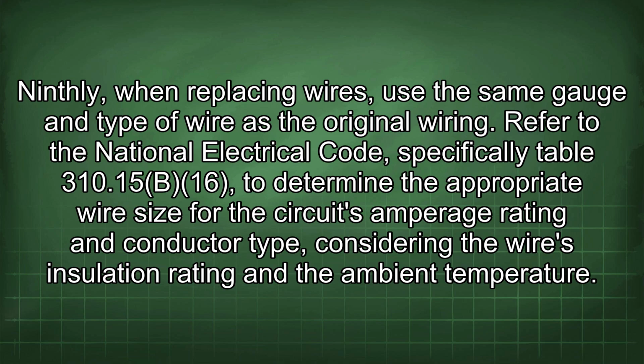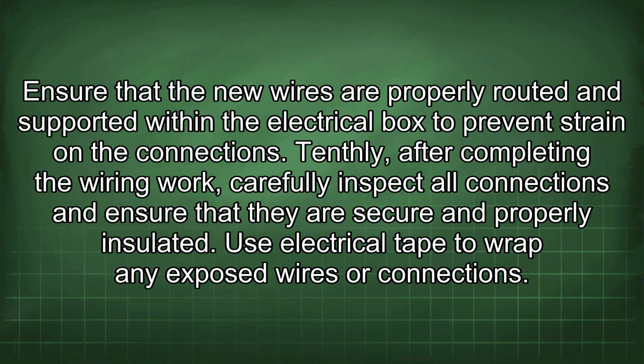Refer to the National Electrical Code, specifically Table 310.15(B)(16), to determine the appropriate wire size for the circuit's amperage rating and conductor type, considering the wire's insulation rating and the ambient temperature. Ensure that the new wires are properly routed and supported within the electrical box to prevent strain on the connections. Tenthly, after completing the wiring work, carefully inspect all connections and ensure that they are secure and properly insulated. Use electrical tape to wrap any exposed wires or connections.